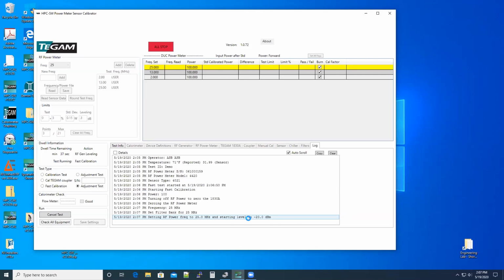And it's set a 1-minute timer to let all the power meters settle. And again, that's a bit conservative. We'll just have to wait for that timer to tick down. When the timer is timed out, it's going to calculate a new signal generator setting and keep at that until we're within this limit here, 0.3 of a dB of the 100-watt set point. Sometimes that takes a couple iterations to get there.